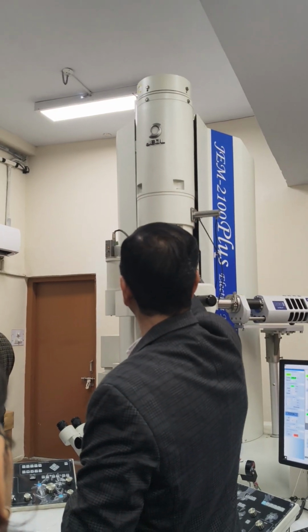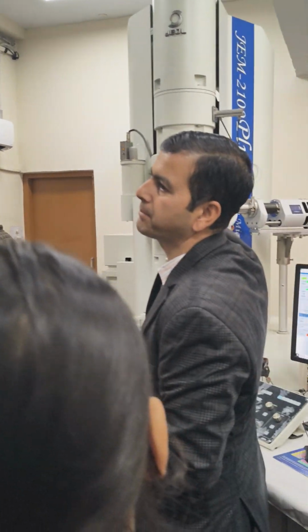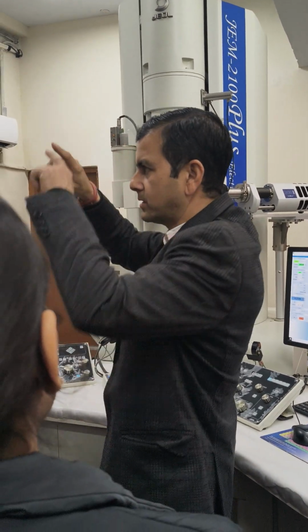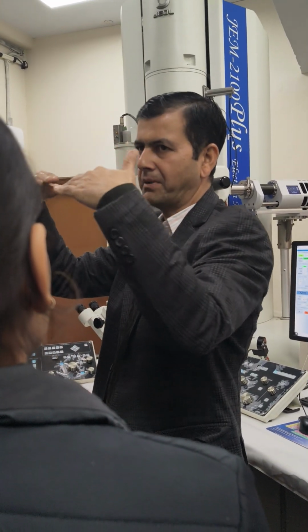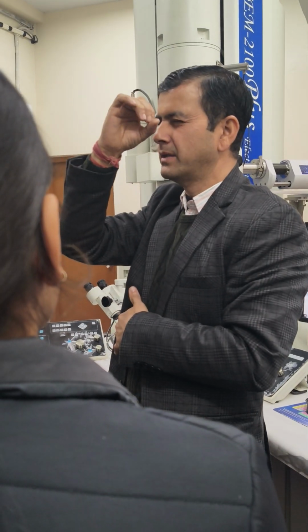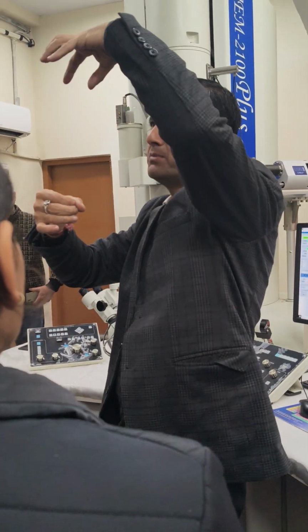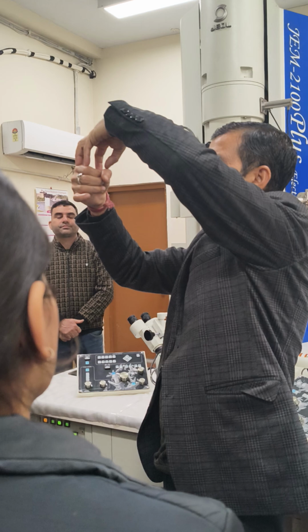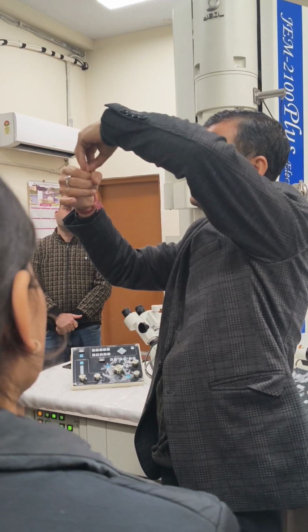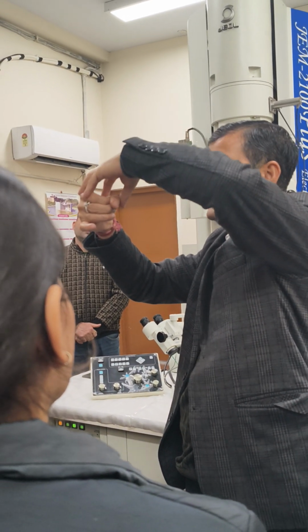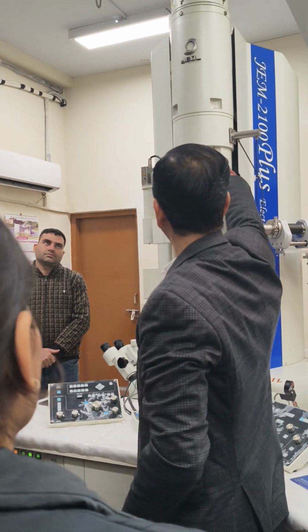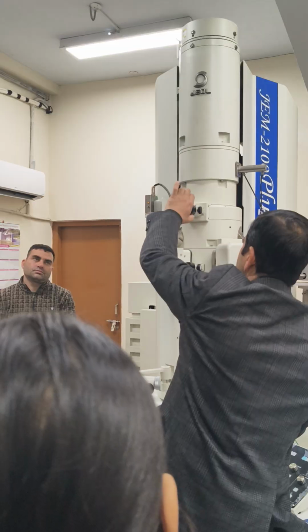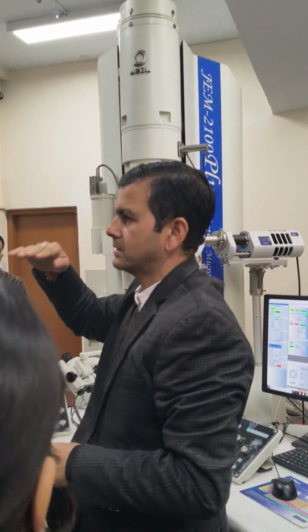Condenser lenses are there, with a movable condenser aperture. As I showed in the diagram, something is removed by putting in a strip-like thing. It has some diameter, and the beam passes through that diameter. Suppose the beam is coming like this, it passes through a narrow diameter, and the extra comes as stray beam, lost in the form of heat, and only a fine beam passes. This is the purpose of this aperture, and you can see we have apertures of different diameters.